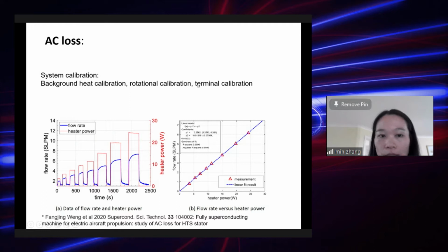so to calibrate the background heat flow and the rotational heat losses and terminal heat losses in order to remove all this heat which might potentially get into the inner measurement chamber. And then we also put in a heater inside the inner measurement chamber. So we fix the power for the heater, measure the flow rate as shown here in the blue one, and then we plot the heat power versus flow rate, a constant plot here.